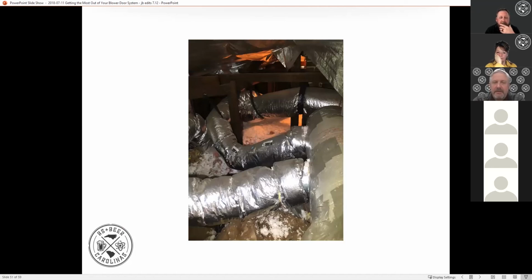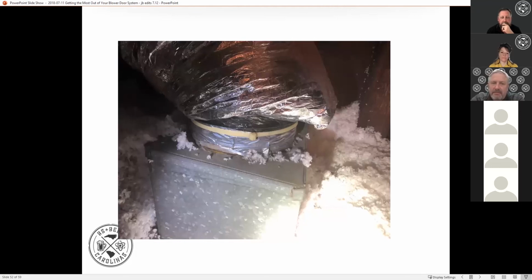You can see there, exposed boots—none of those saddle collars had any balancing dampers in them, so there's no way to control flow to rooms. Right now everything is taking the path of least resistance, so we're not able to tweak this. You can see the inner liner, it's in bad shape all the way around.